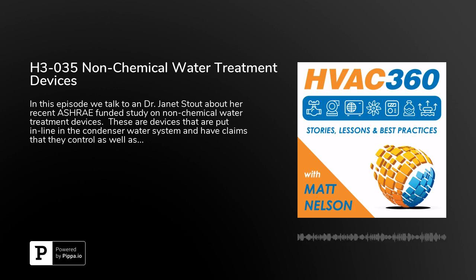And that's, I think, one of the most important messages for the users of these devices: you can use them safely, but you may need to verify whether or not Legionella is under control with whatever treatment you have, whether it's chemical or non-chemical. And the way to do that is to monitor for Legionella. So that's kind of the cautionary tale from my perspective on this study: you really need to be monitoring not only for total bacteria in your cooling towers, but also for Legionella to assure that you're not amplifying a potential public health concern there.